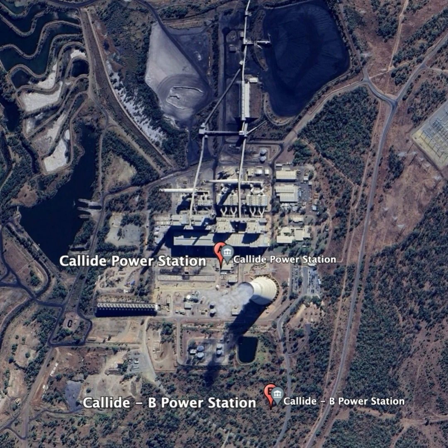At this time, the AEMO Energy Management System, EMS, showed that C4 was sinking 50 megawatts and 300 megavars from the grid, though the line voltage of 275 kV at the Callide substation was still holding. At 1:49 p.m., the Callide control room was evacuated to ensure the safety of personnel.